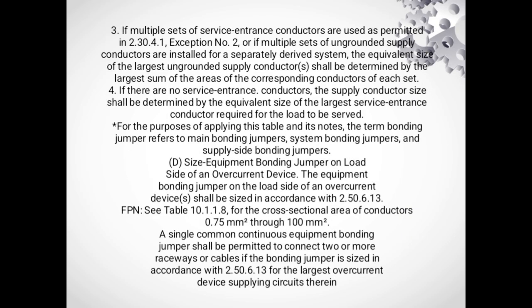3. If multiple sets of service entrance conductors are used as permitted in 2.30.4.1, exception number 2, or if multiple sets of ungrounded supply conductors are installed for a separately derived system, the equivalent size of the largest ungrounded supply conductor shall be determined by the largest sum of the areas of the corresponding conductors of each set. 4. If there are no service entrance conductors, the supply conductor size shall be determined by the equivalent size of the largest service entrance conductor required for the load to be served. For the purposes of applying the table and its notes, the term bonding jumper refers to main bonding jumpers, system bonding jumpers, and supply side bonding jumpers.